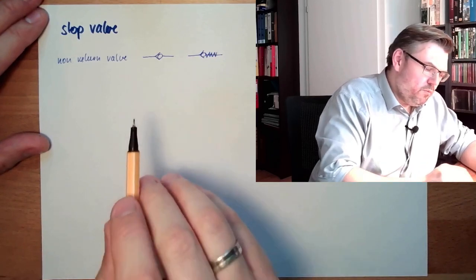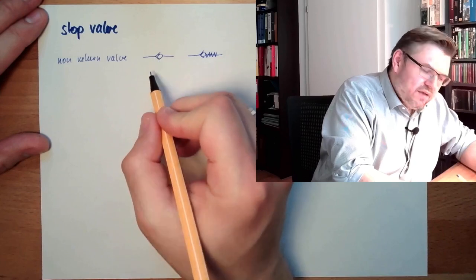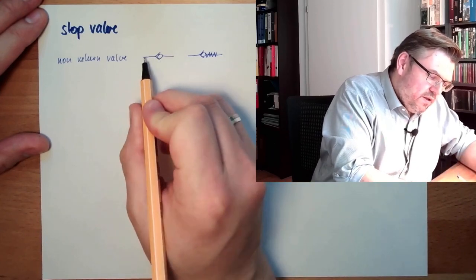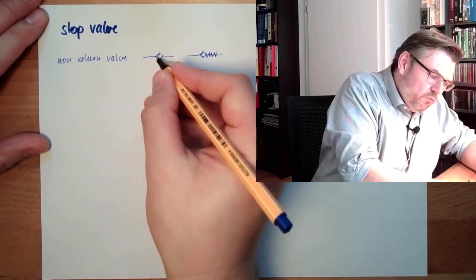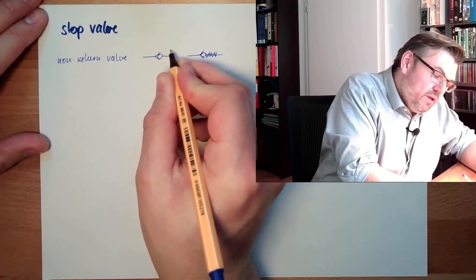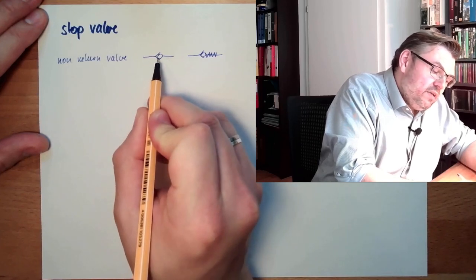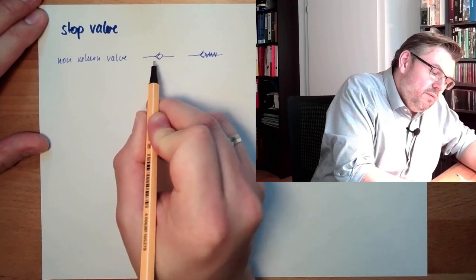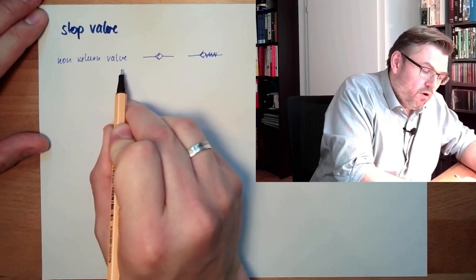You can think about this circle here as a ball and this as a seat. If pressure comes from here and here is no pressure, this ball will be pressed against the seat and will seal here, so there is no air coming through. If pressure is here higher than here, this ball will be lifted off the seat and air can stream by. So air from here to here is no problem; from here to here it's blocked. Non-return valve.